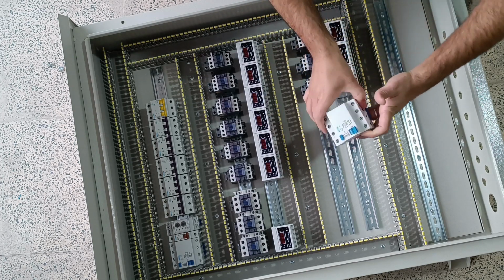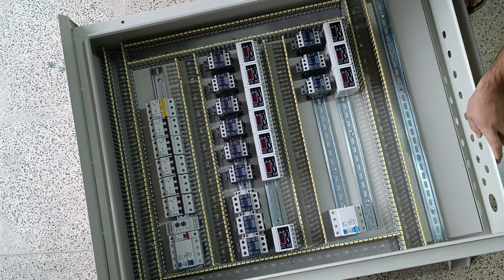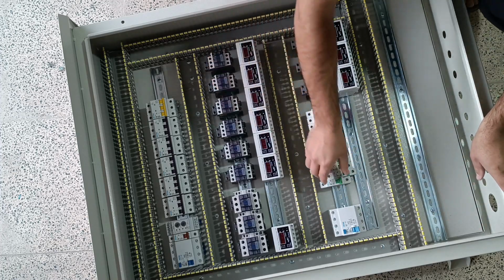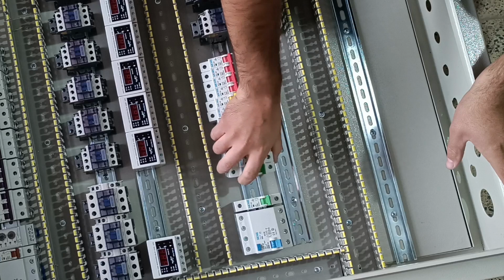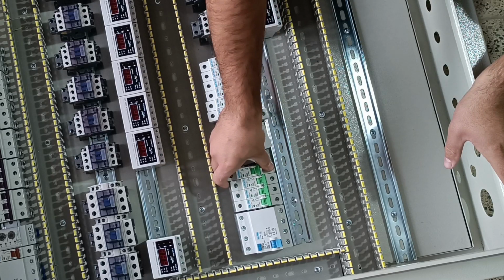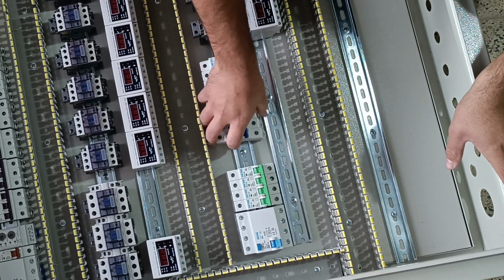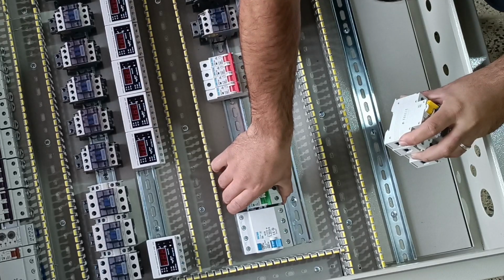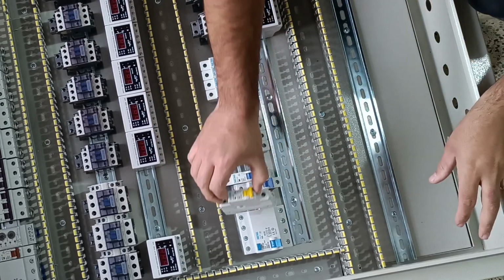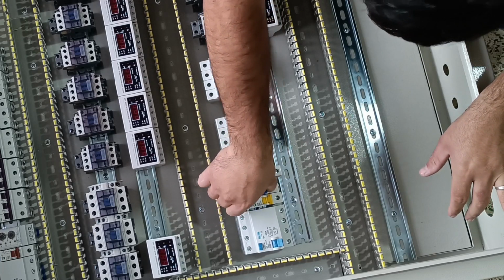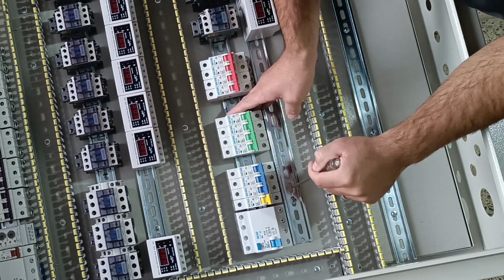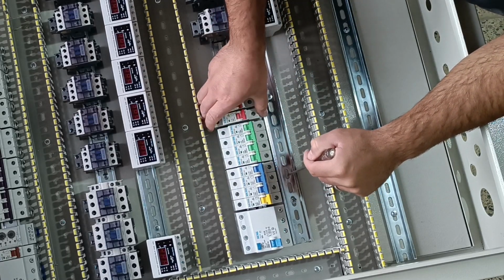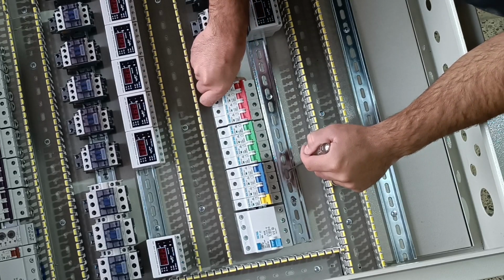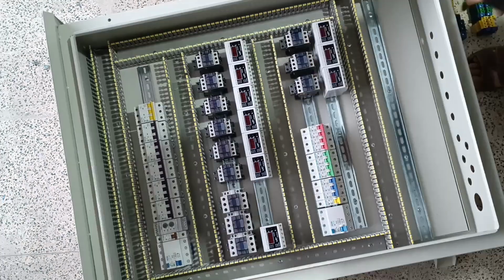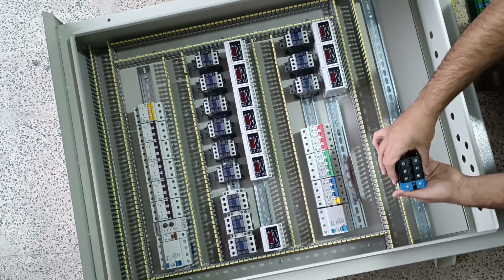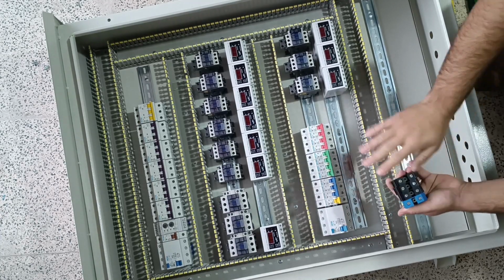In this switchboard, there are 12 single-phase outputs, for all of which we use a RCCB switch. And for each single-phase output, we consider a single-phase miniature switch separately. Now we install the input and output terminals. These 4 terminals are for neutral and 3-phase input to the switchboard. The electricity enters the electrical panel from these terminals.